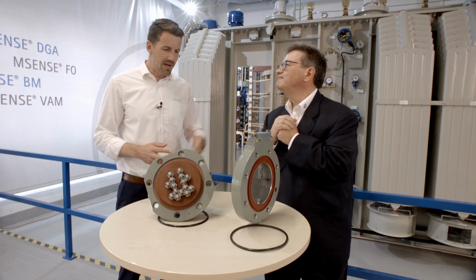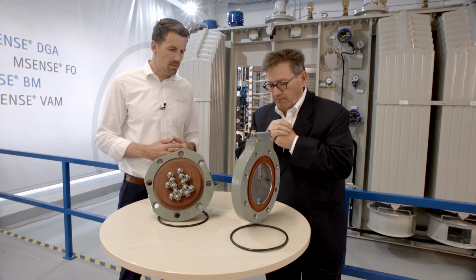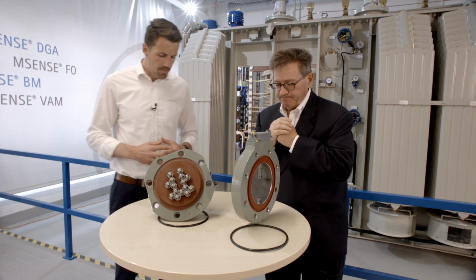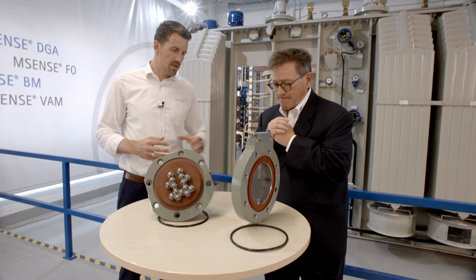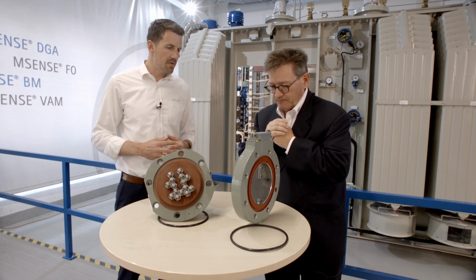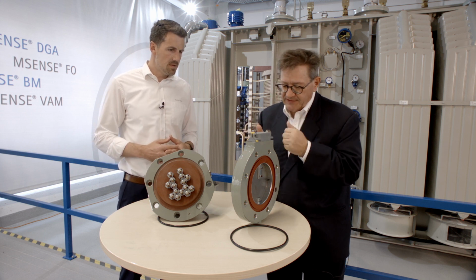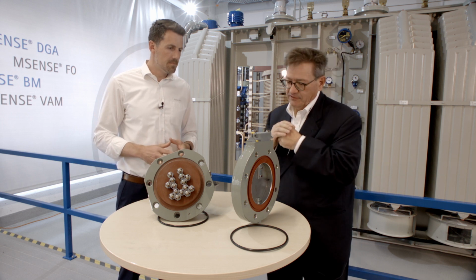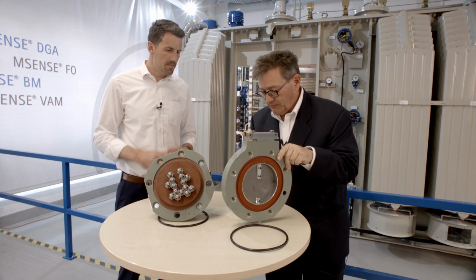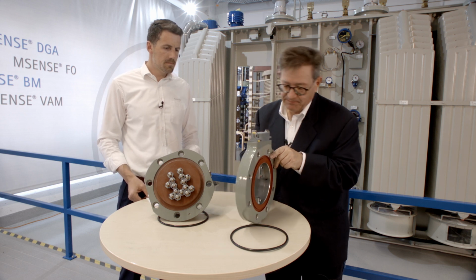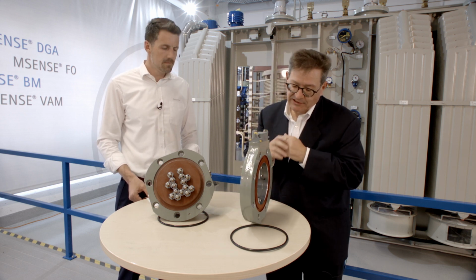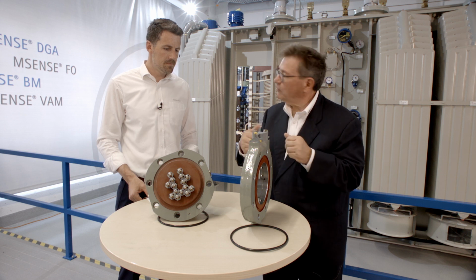Okay. On the left-hand side, Tullio, we see here a butterfly valve. Talking about that one here specifically, what kind of butterfly valve did you bring along with you? This is an isolation valve, what we call a butterfly valve, because the plate here is rotating by 90 angular degrees to close and open the oil flow. Obviously, this is a manual valve to be installed in any oil pipeline in the power transformer.